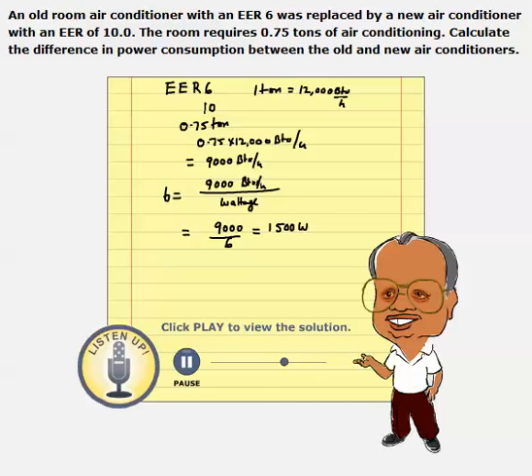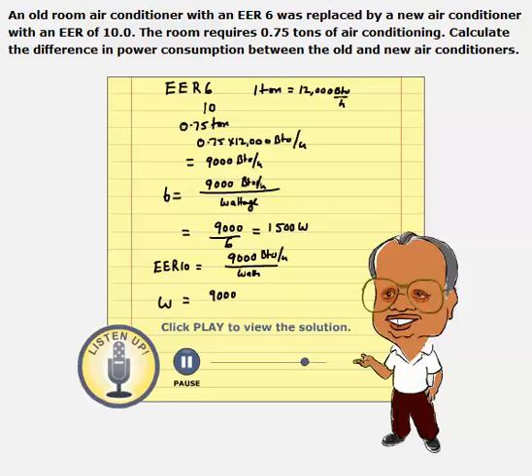Now, if we were to replace this with an EER of 10 air conditioner, it still has to pull out 9,000 BTUs per hour. What would be the wattage? Watts equal to 9,000 BTUs per hour divided by 10. That would be 900 watts. So by replacing this air conditioner, which used to consume 1,500 watts, with an energy-efficient air conditioner with an EER of 10, we are able to bring down the power consumption to 900 watts.